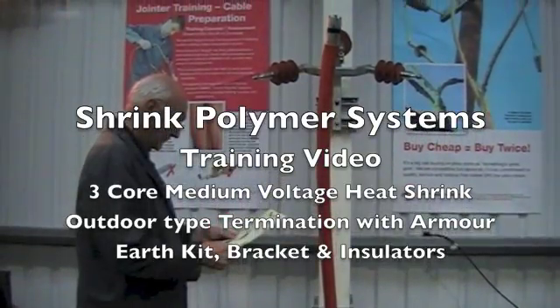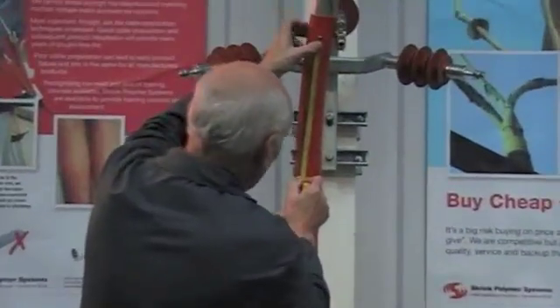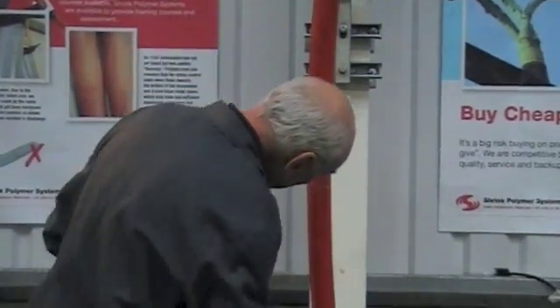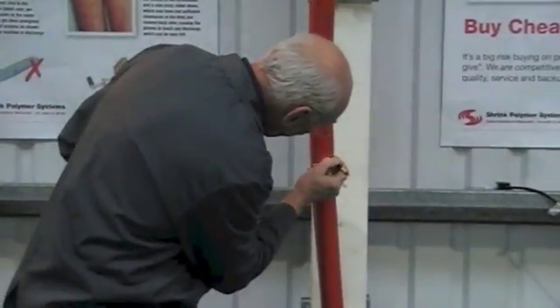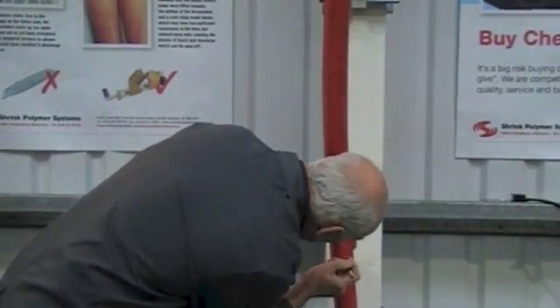We're going to show you the installation of a three core outdoor heat shrinkable termination. This could be for 12kV, 24kV, or 33kV XLPE cable. The only difference will be the number of rain sheds and some of the components will be longer.